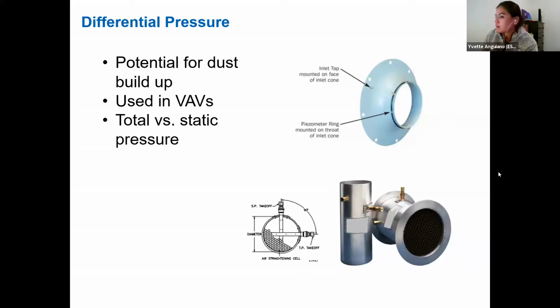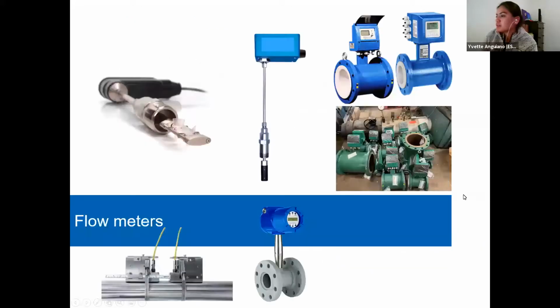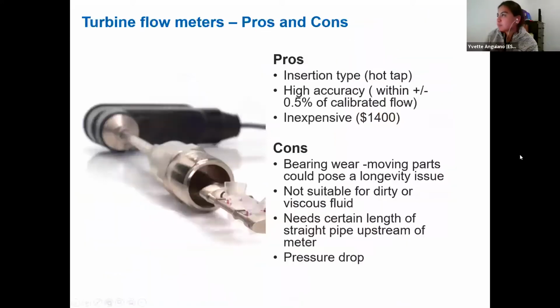And so the last topic I want to cover is flow meters. There are many types of flow meters as well, and we've only selected five of the more prominent types to cover today. The first kind of flow meter is a turbine flow meter, and there are many reasons why they're great, and reasons why you may not want to select them. This is an insertion type, which means that it can be hot tapped, so you don't necessarily need to shut down your system if you have an existing system to install this type of flow meter. They're incredibly accurate and inexpensive compared to other styles.